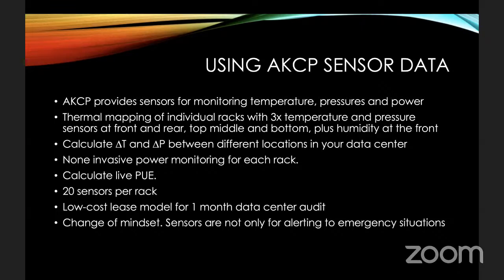If the servers are sucking 3 cubic meters of air per second, and your air supply is only 2 cubic meters of air per second, you're not cooling enough. Your servers are going to overheat. They're going to be running their fans at a higher speed. The servers are going to consume more energy. They're going to be able to do less work. They're going to last less time.